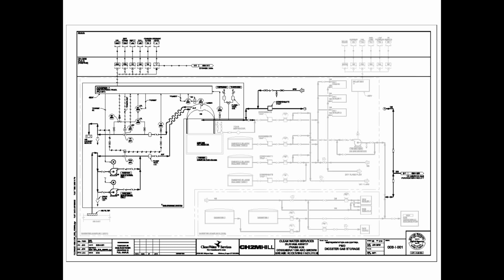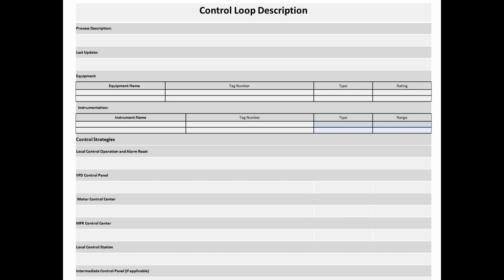But many times PLC programmers, while they are very good at programming PLCs, really don't know the wastewater process as well as you might. So in that case, they need a lot of verbal instruction, and for that they need what they call a control loop description. This is a blank control loop description, but it has the information that a PLC programmer would need to know in order to write the PLC program. It starts off with a short description of the process and how the process is designed to work.